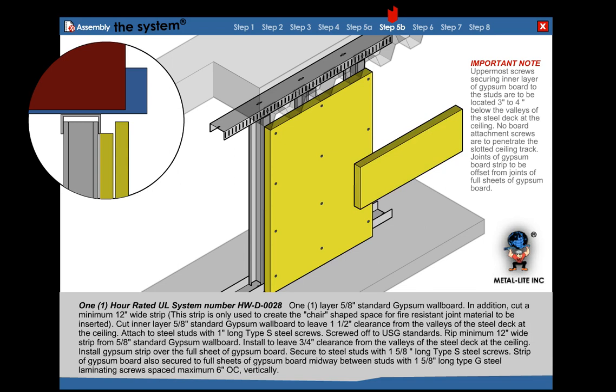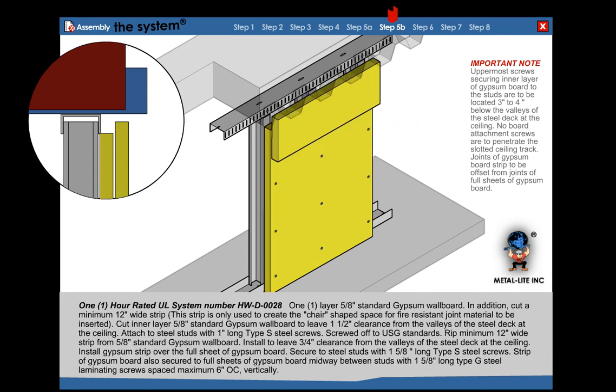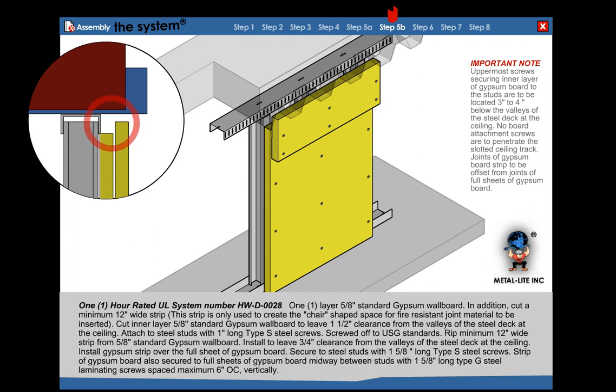Rip a minimum 12 inch wide strip from 5/8 inch standard wallboard. Install to leave 3/4 inch clearance from the valley of the steel deck at ceiling. Install strip over the full sheet of gypsum board on each side of the wall. Secure to steel stud with 1-5/8 inch long Type S screws. This rip will create the chair system.